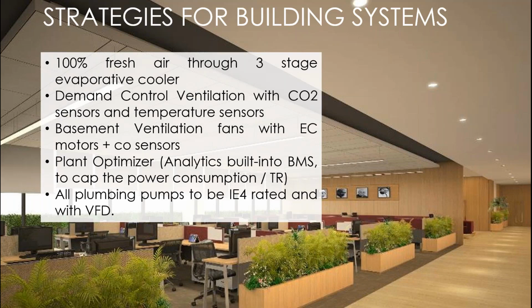But what about the oxygen? Whether it is winter, whether it is summer, don't I require that minimum critical airflow into my room? So in this particular building, we simply did not link the air conditioning system with a thermostat. We linked it with a CO2 sensor as well, and we made sure that every room will also get that minimum bleed, because when the ministers are sitting there, one of the conditions, though not a part of the RFP document, was that the air quality in Delhi is very, very poor, especially during those winter or the transition months. So we also made sure that this building takes care of that.